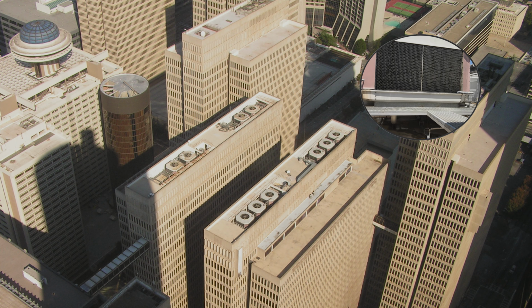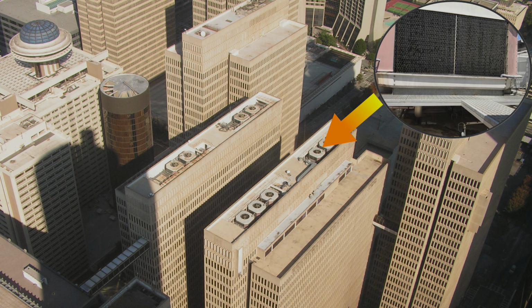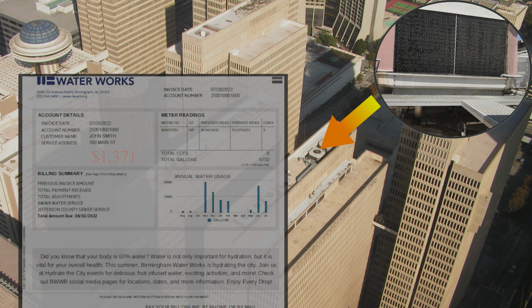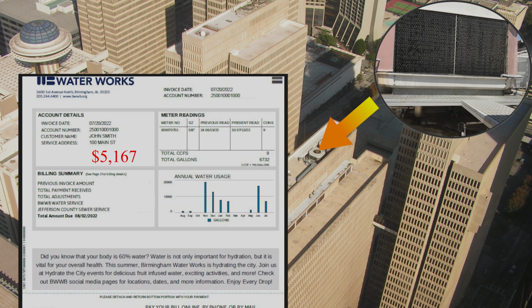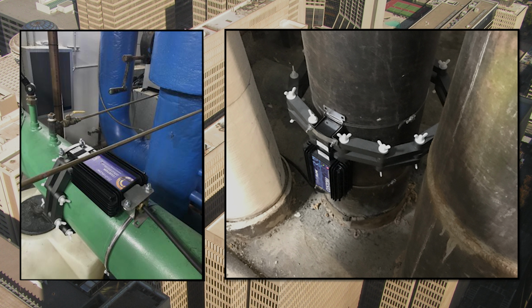This project involved cooling tower optimization at one of the buildings of a large commercial complex in Georgia. Due to high water costs, the cooling towers were operated at high conductivity to reduce water usage, which resulted in severe scale and biofilm problems. HydroFLOW units were installed indoors on the recirculating water loop of the cooling system prior to the chillers.